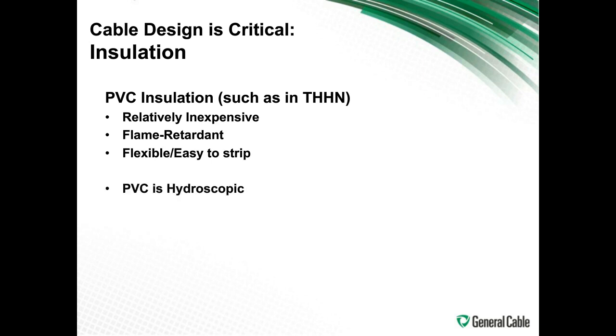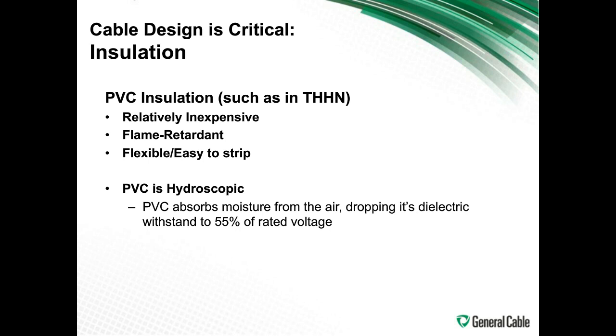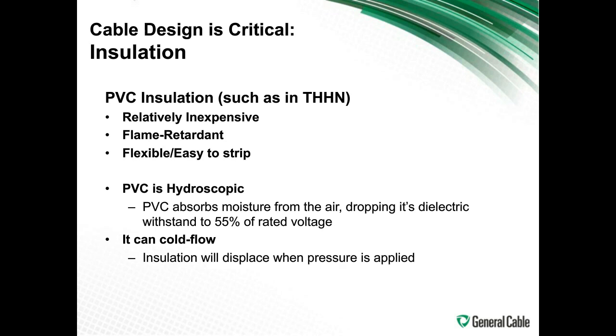But the negative aspect is that it's hygroscopic. What that means is that it can absorb moisture from the air. Even if you don't have water near you, it's going to take it from the air and change the actual capacitance of the cable and drop its dielectric. That changes the electrical properties of the cable itself. Another phenomenon is that it can cold flow. So what does that mean? If you have some type of pressure on the cable, over time that insulation will be displaced by that pressure, and the thickness will actually go down. When that happens, you're going to see a change in the way that it behaves and an impedance change in the cable.